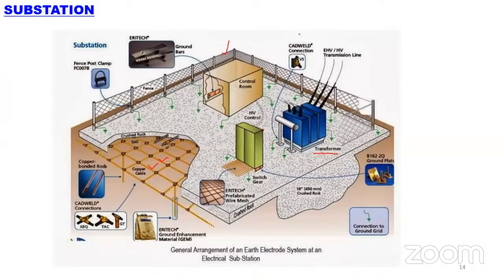This is for the safety of the operator. For example, if a person is standing on the ground and a fault occurs on the transformer or any equipment, earth fault current flows into the ground through this conductor mesh, called the mesh or grid, which helps distribute the earthing current across the ground so the person standing there does not get electrocuted.